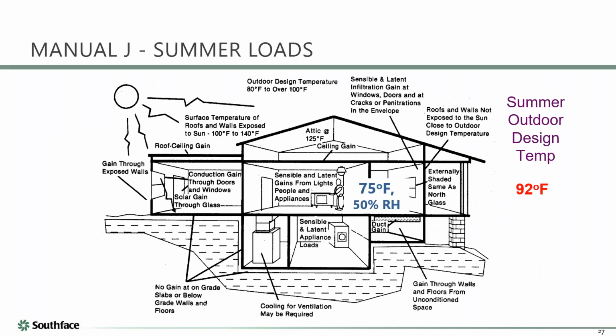And you can oversize the furnace a little bit and still be well within good graces. In the summertime, it's the same thing, only the heat flow is going a different direction. It's going from 92 to 75. It's gaining into the house. It's got a higher delta T across the attic. And we are now going to account for the solar gain through the windows. And we are going to account for the internal gains of the lights and people and appliances and so forth.